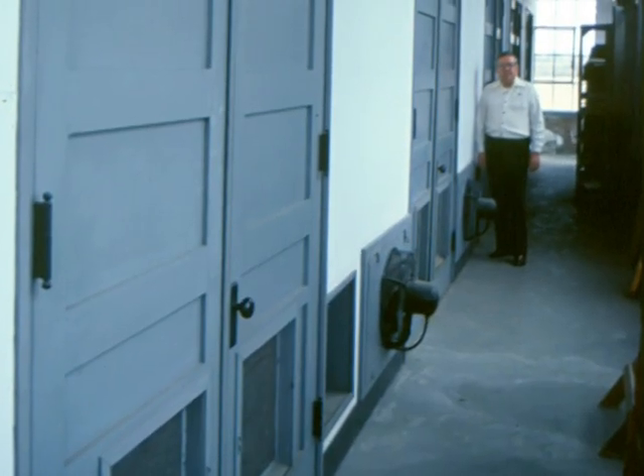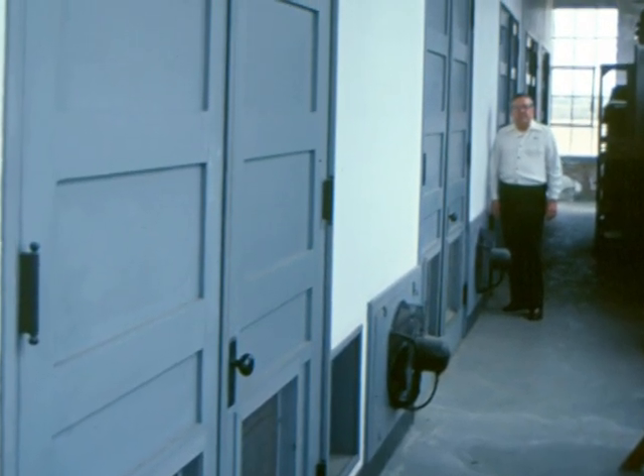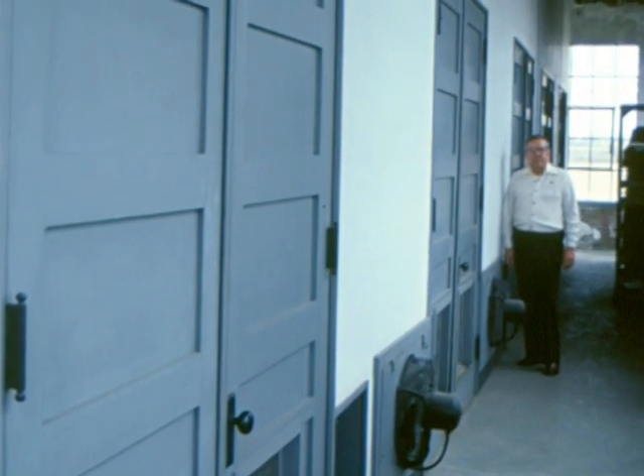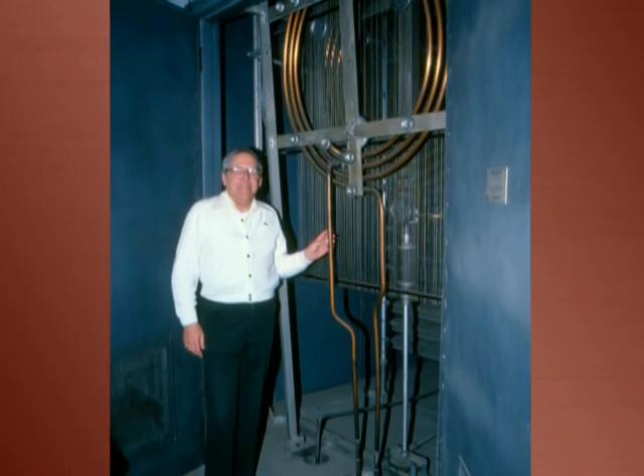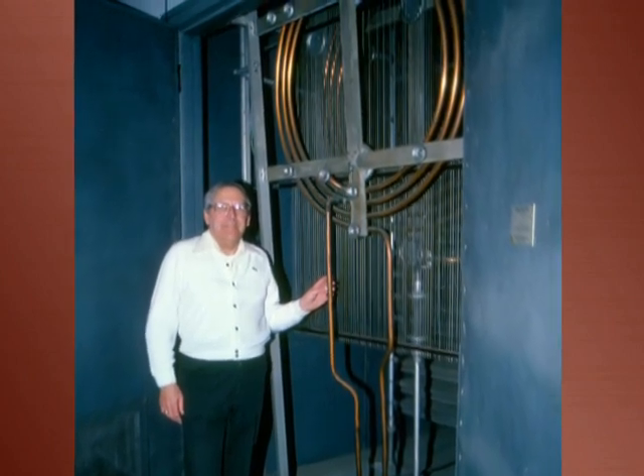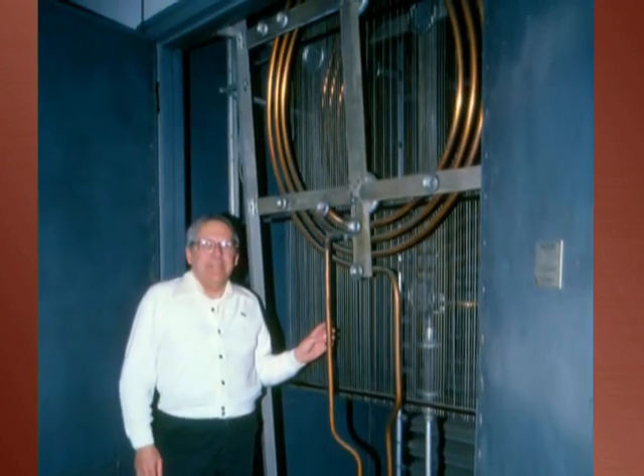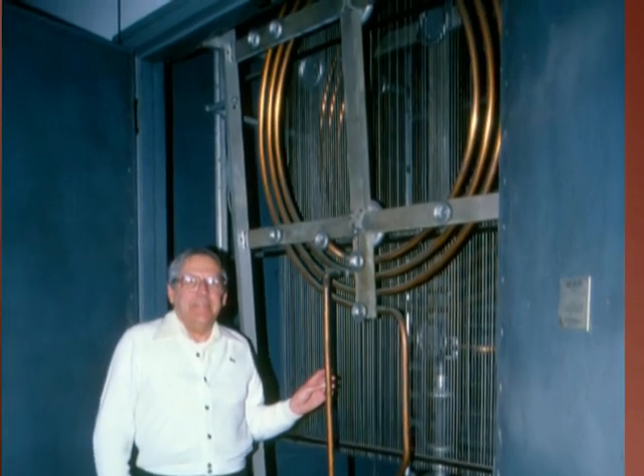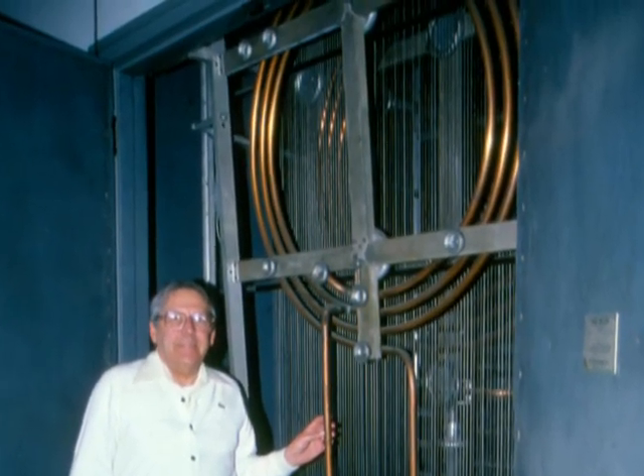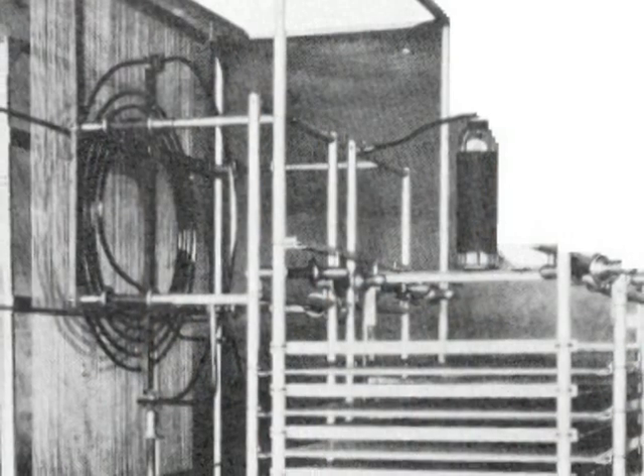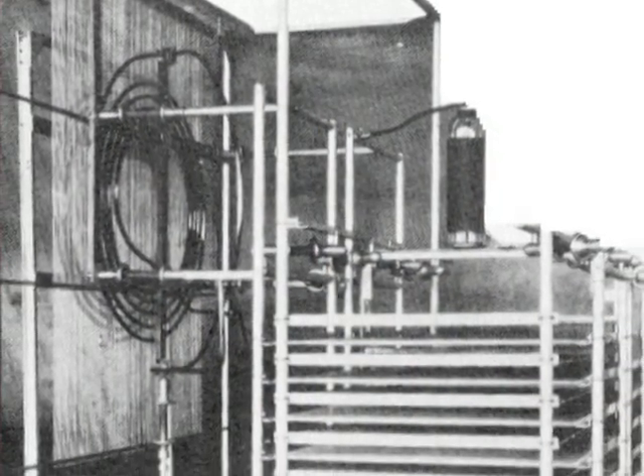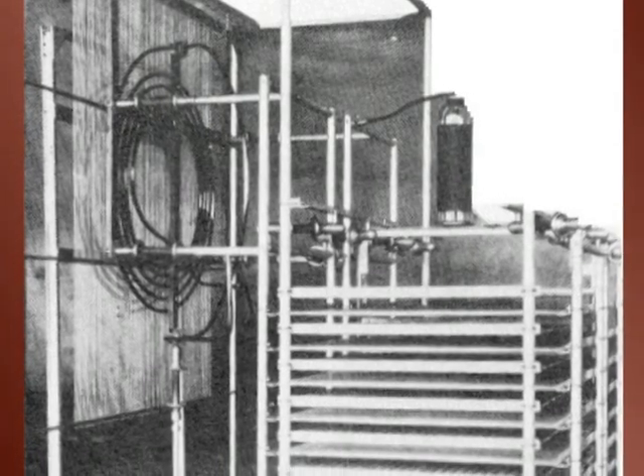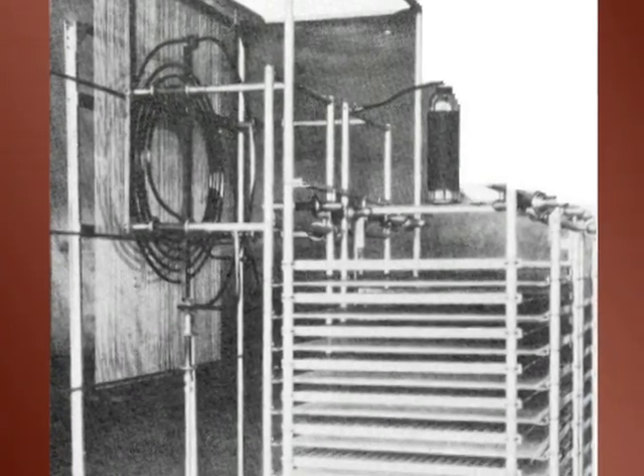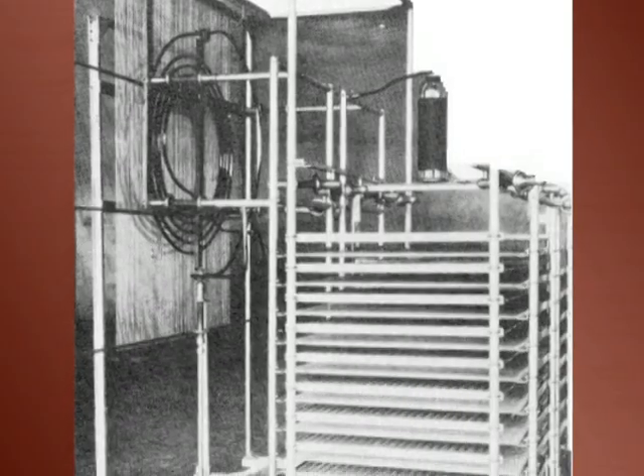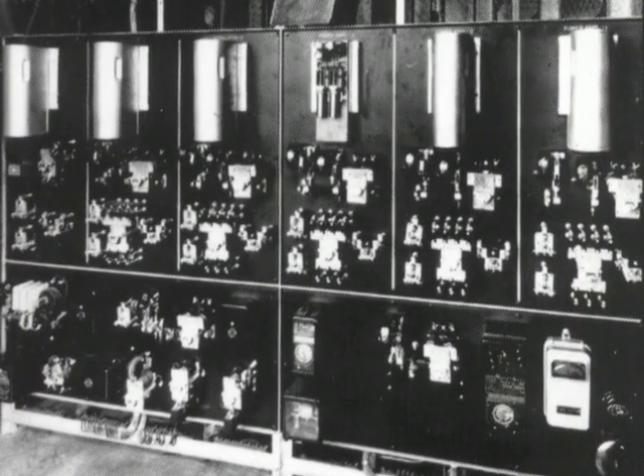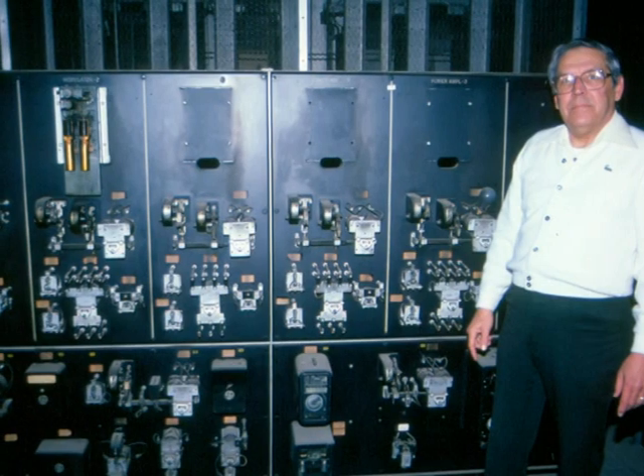In the back of the transmitter, pairs of metal-lined doors provide access to the rear of each of the 6 cubicles. The door to the rear of power amplifier number 1 provides access to the spiral coupling coil, the variable plate tank coil, and the fixed plate tank capacitor. Note the Faraday shield and the 1-inch aluminum pipe construction of the plate tank capacitor. Power amplifiers number 2 and number 3 are of identical construction. Behind the rectifier cubicle, the relays for the control circuits are panel mounted.